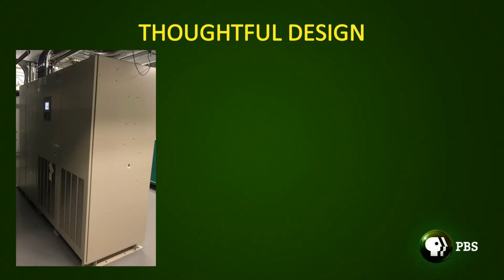I don't have a great deal of love for the little individual rack UPSs where you have to have one in every rack, because as soon as you get more than 2 racks or so, then you've got a maintenance monitoring challenge that can catch you by surprise. So, no, that's the reason I'm not a big fan of those.